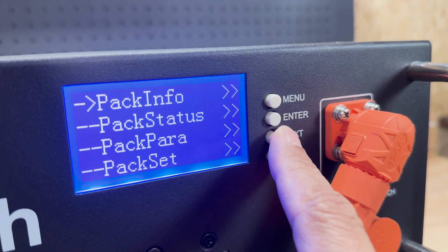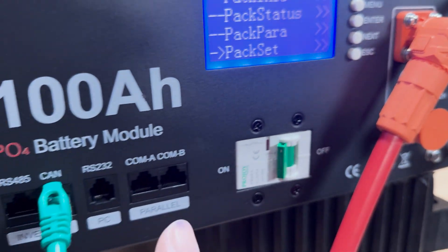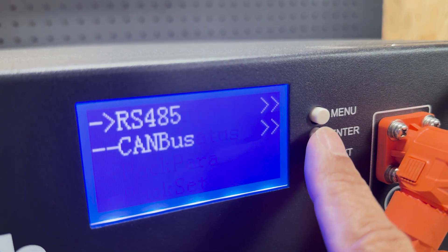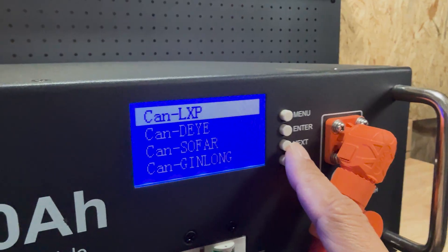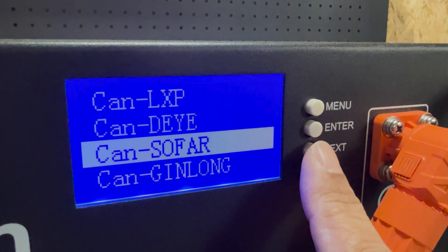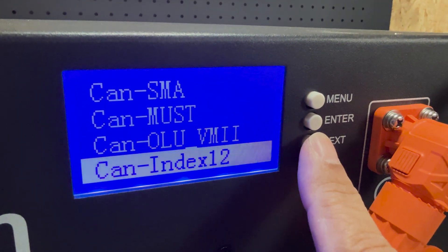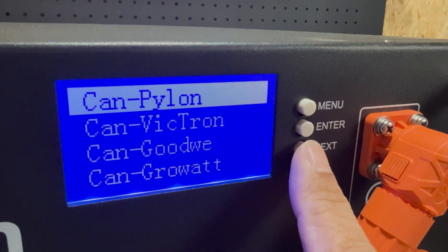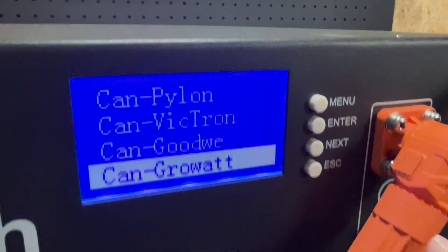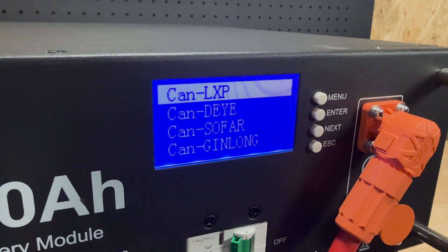You can see the pack information on the front. We're going to go into pack settings to set the communication for the CAN cable. Going into the menu — it's got LuxPower, Deye, Ginlong, SMA, Pylon, Victron, Growatt, and a bunch of other protocols. We're going to set it back to LuxPower.